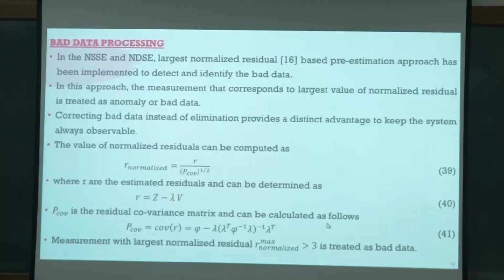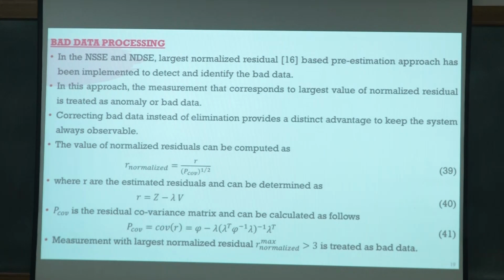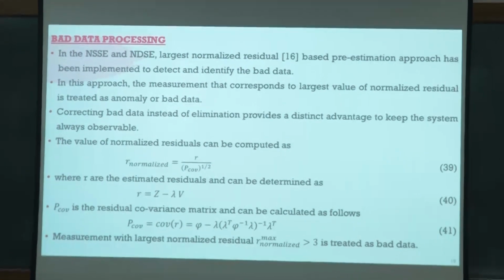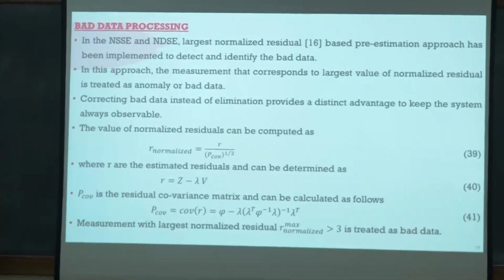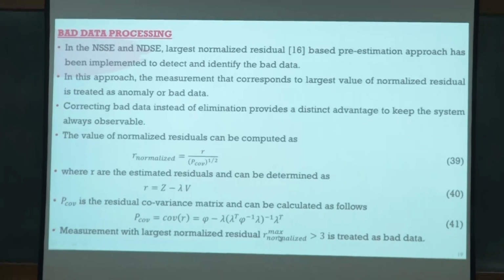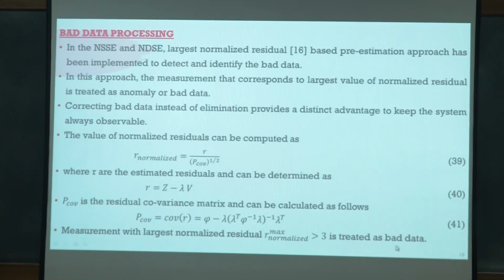Why is 3 used? If you recollect the normal distribution, in the vertical direction, what do we plot? We plot the probability density function. In the horizontal direction, we plot the variable for which we are giving the probability density function. In a normal distribution, it extends from minus 3 sigma to plus 3 sigma. So anything above 3 sigma, or as it is normalized, anything above 3, will be treated as bad data because it lies outside the distribution. So when the maximum value of the normalized residual is greater than 3, it is treated as bad data.